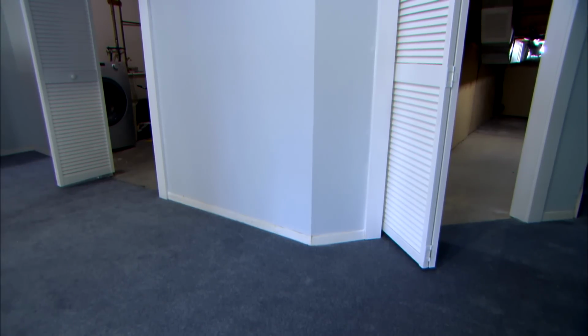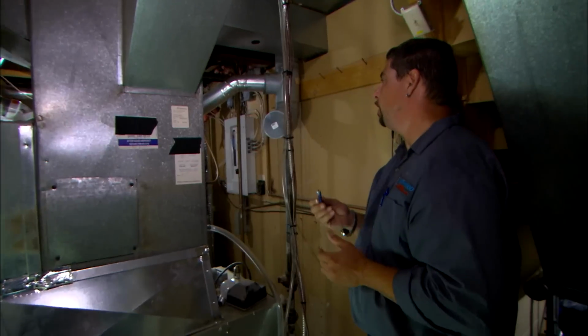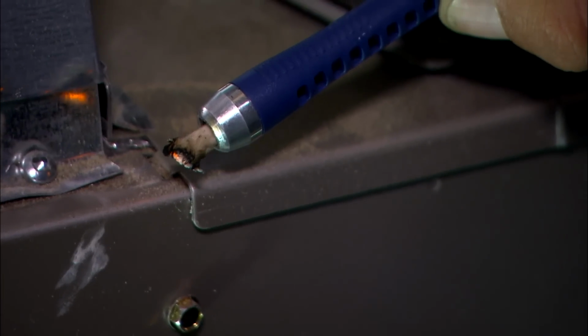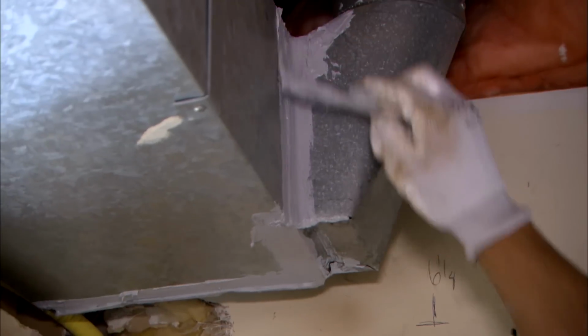I like what Gary did. He first did an air test with CFM, the little meters we had, then a smoke test around the furnace, which showed major bleeding of air coming off the furnace and the main trunk line. Since then, we've taped everything up and siliconed the furnace.